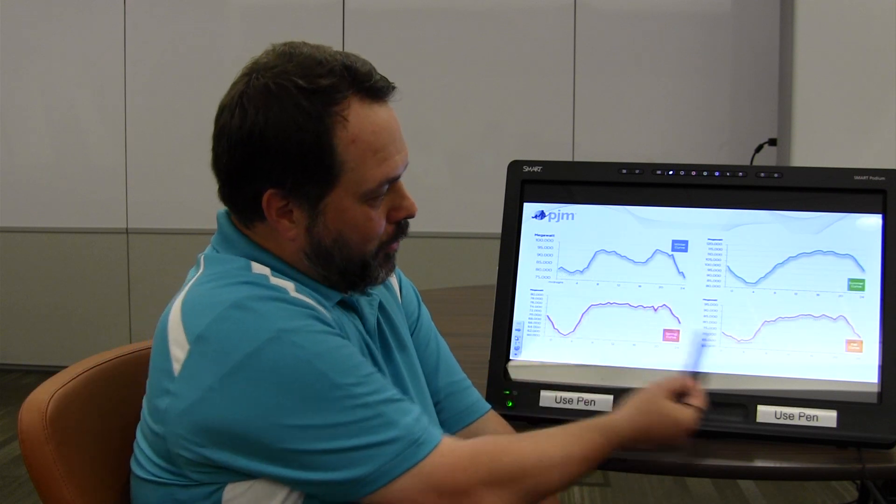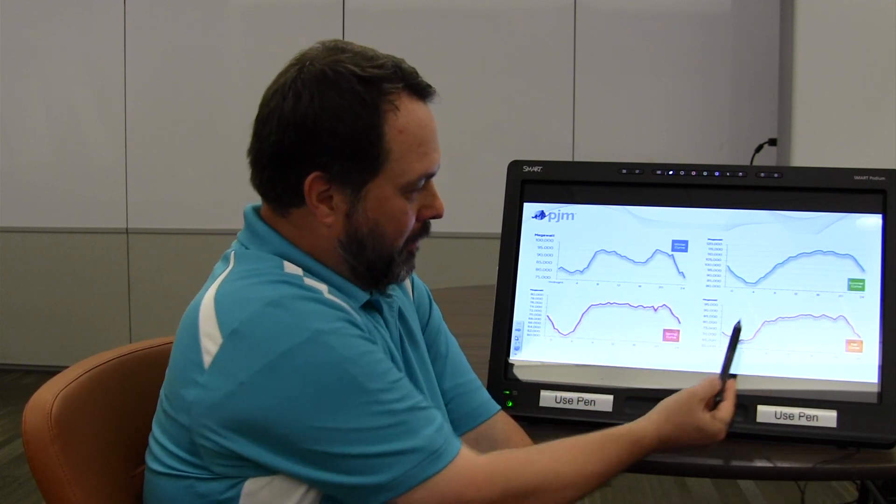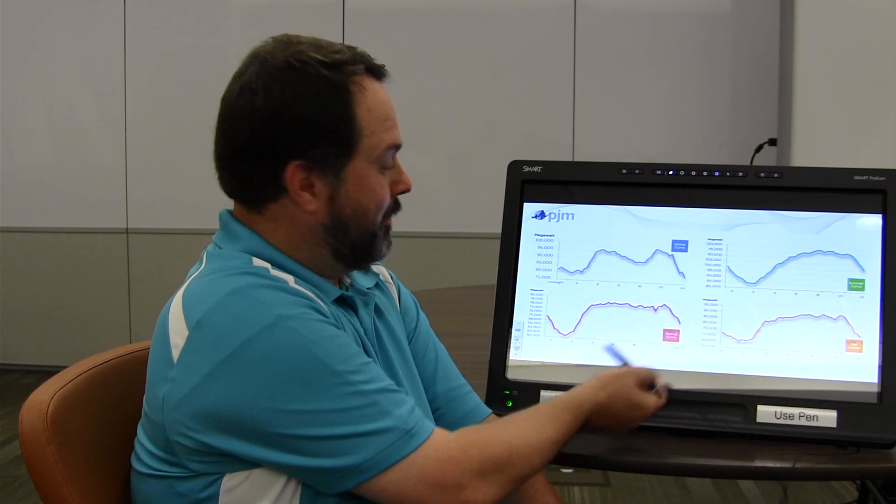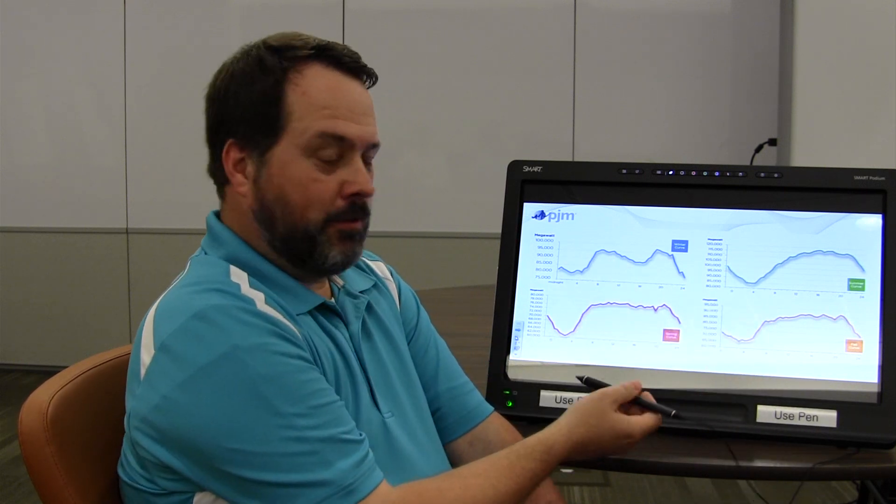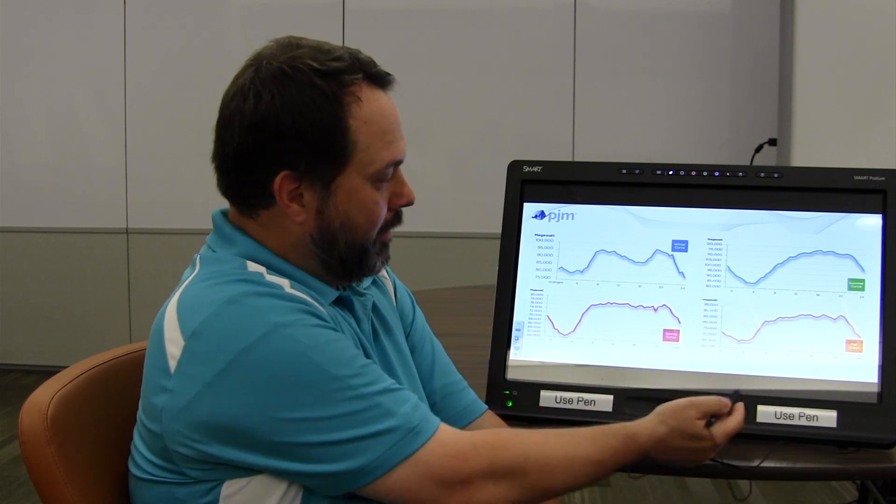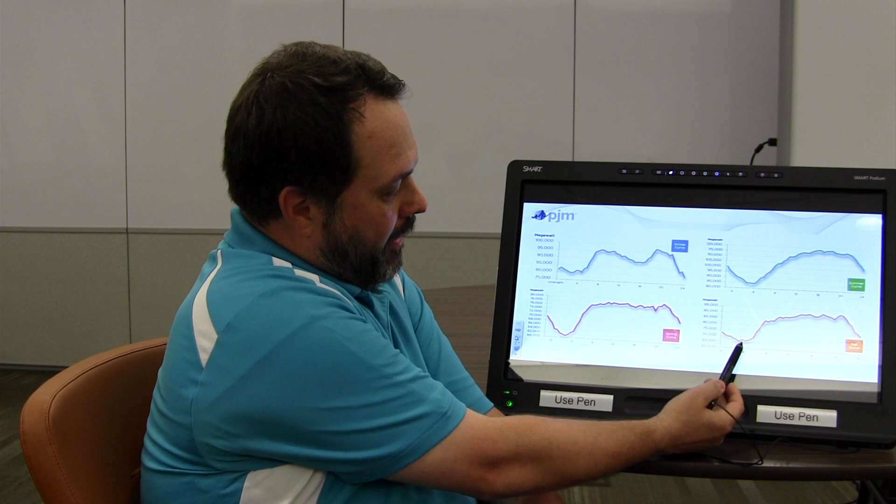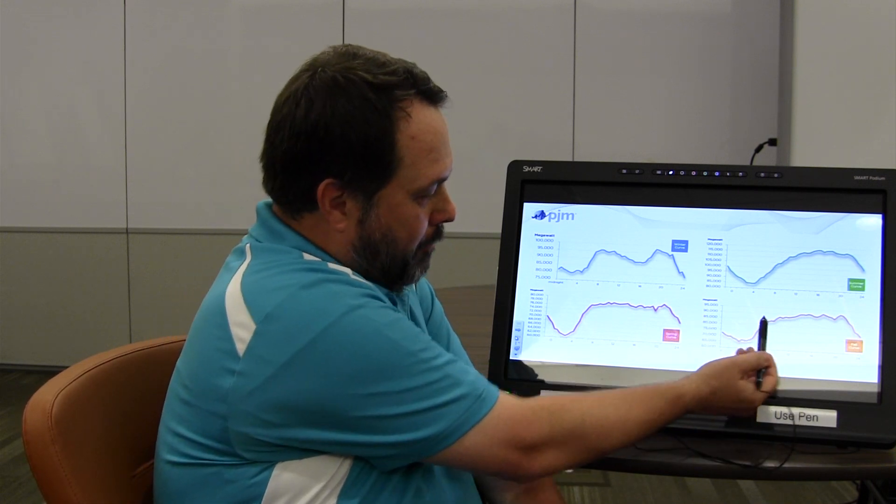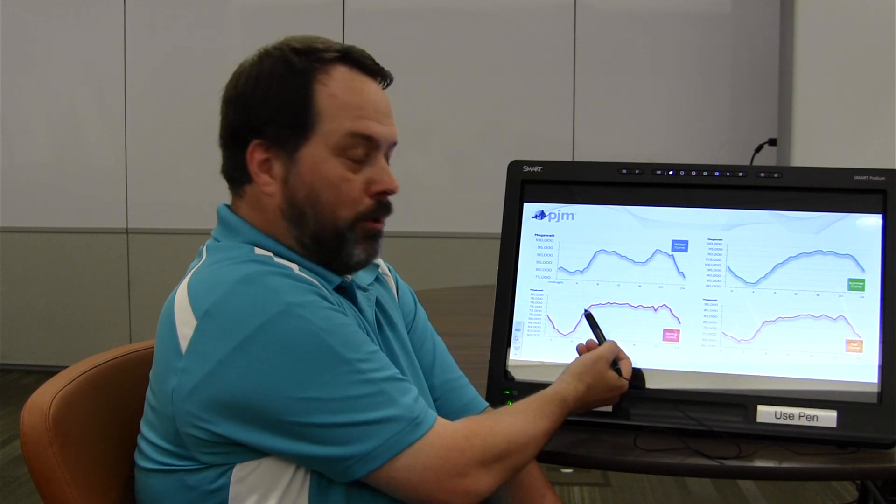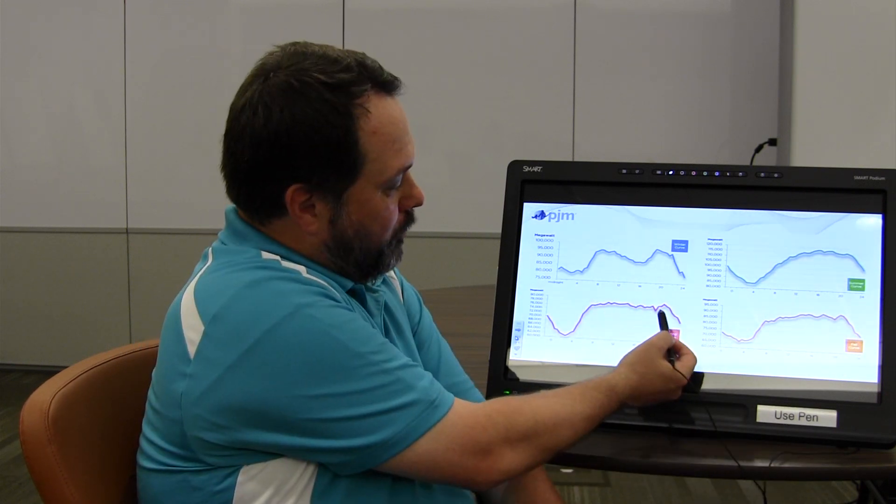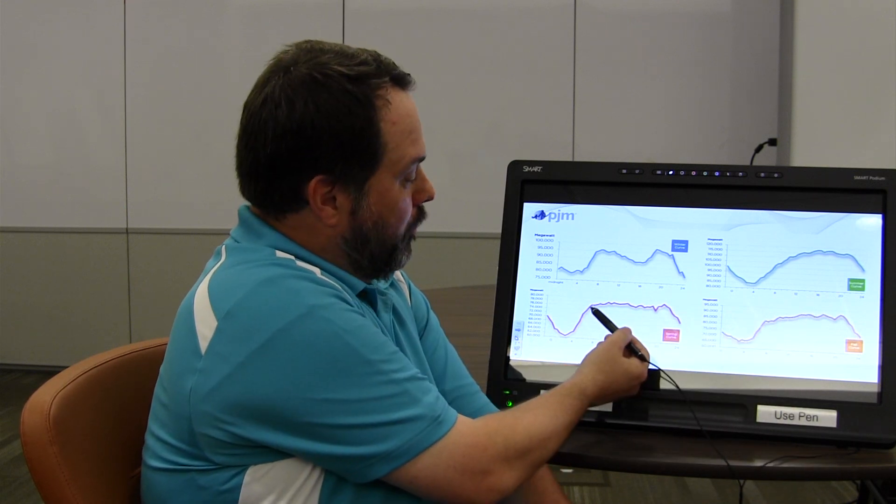The spring curve and fall curves, they're very similar. They're basically hybrids of the winter and the summer curves. So during the spring and the fall, you can see the pickups are a little bit steeper. That's because it's normally chilly still in the morning, so more heat is staying on. The temperatures throughout the day don't change that often, so the load remains basically pretty steady.